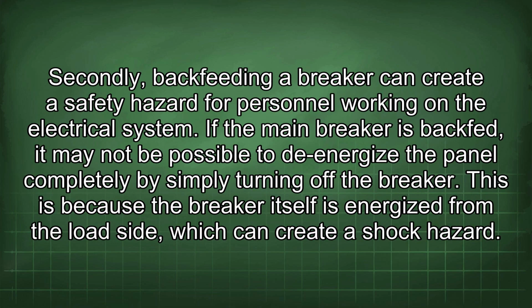Secondly, backfeeding a breaker can create a safety hazard for personnel working on the electrical system. If the main breaker is backfed, it may not be possible to de-energize the panel completely by simply turning off the breaker. This is because the breaker itself is energized from the load side, which can create a shock hazard.